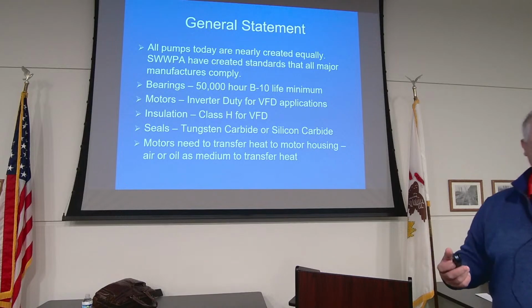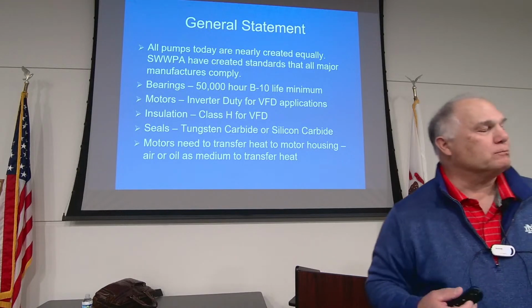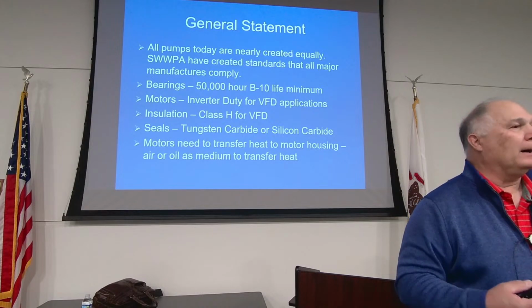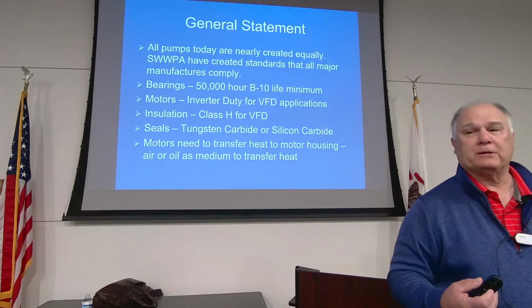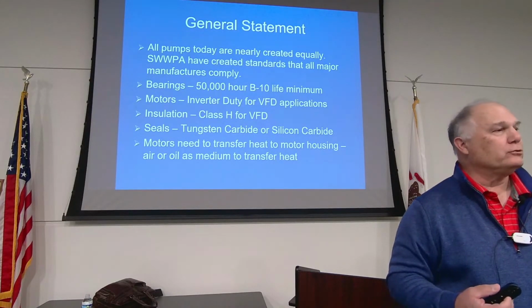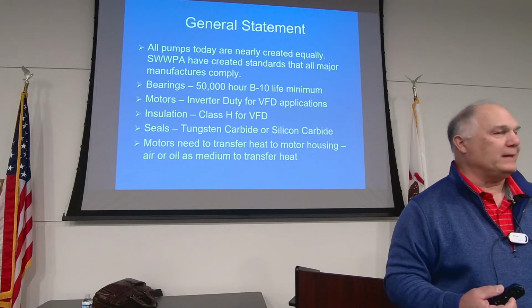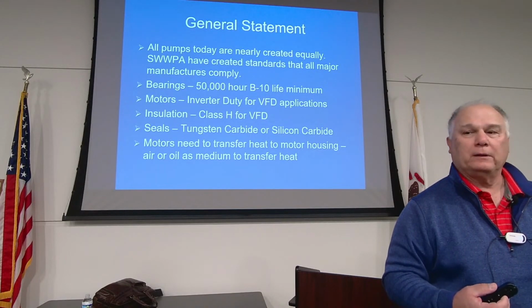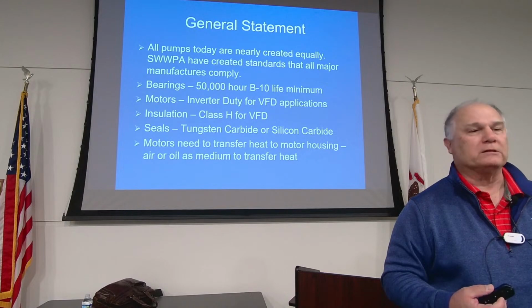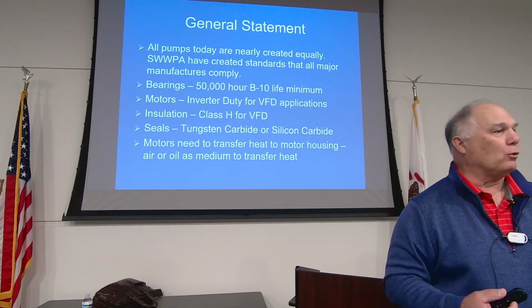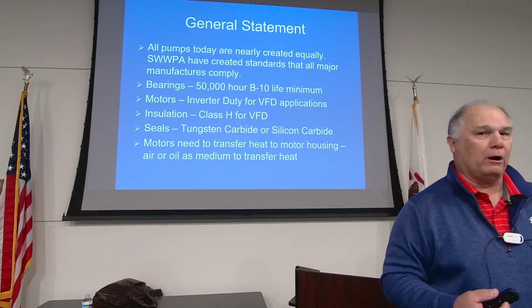Seals. There's a big difference in seals today. The smaller pumps usually have carbon ceramic seals, which are pretty soft. So if you're operating in a gritty application, that's going to scour pretty quickly and therefore fail relatively soon, versus a tungsten carbide or a silicon carbide seal, which are very hard.